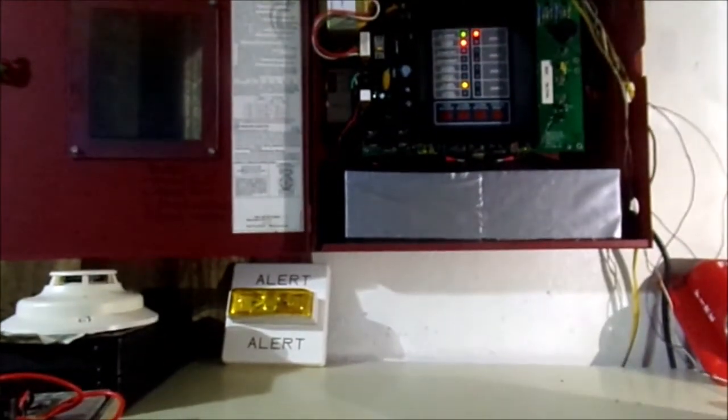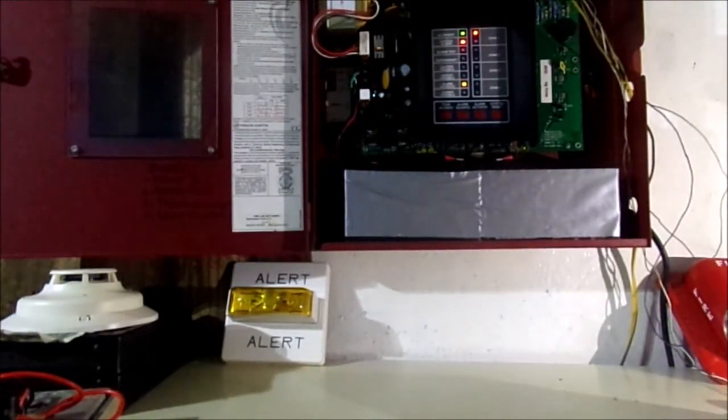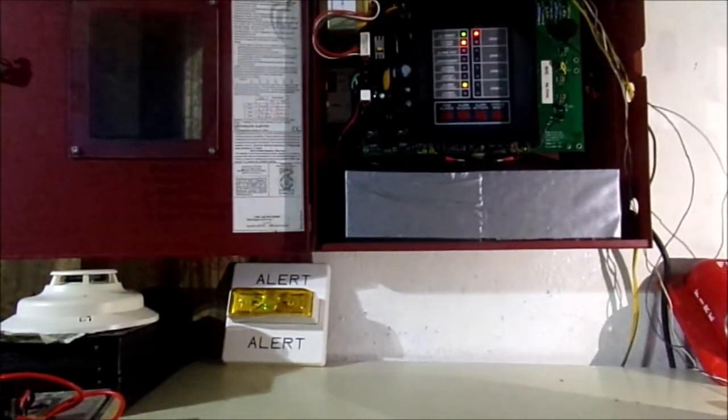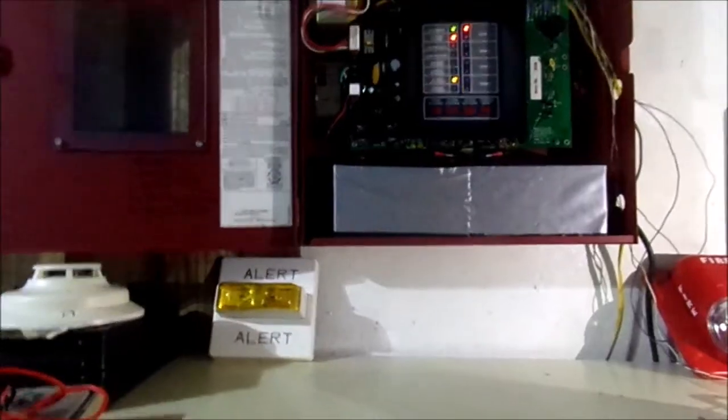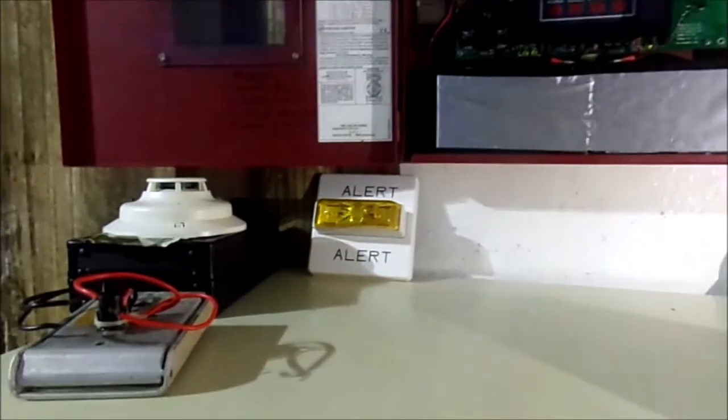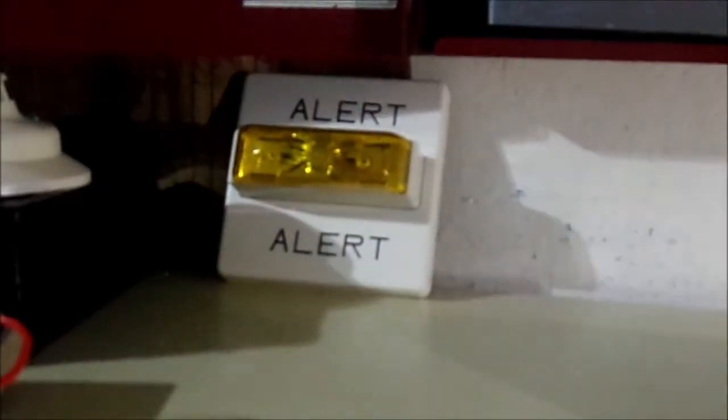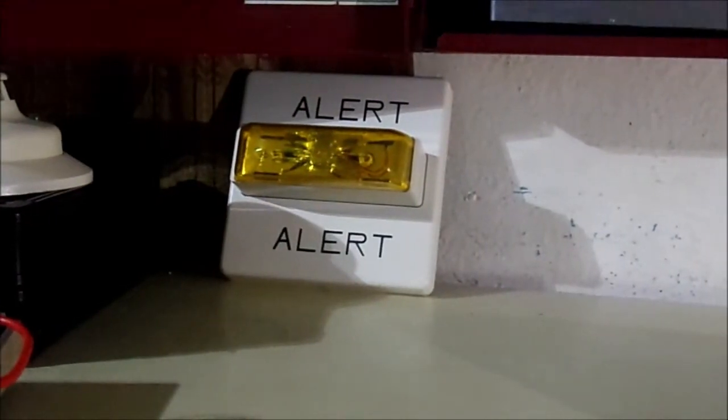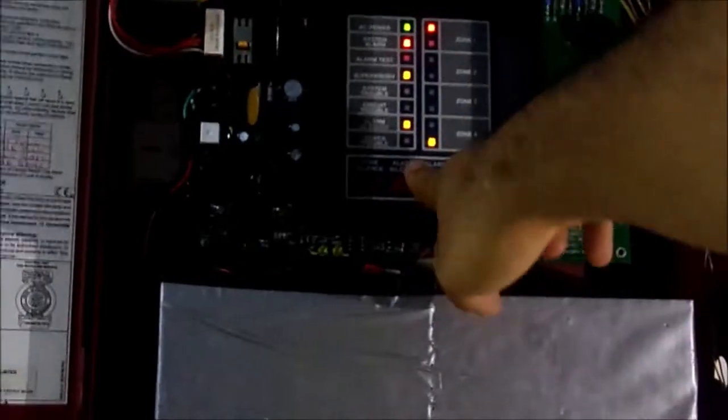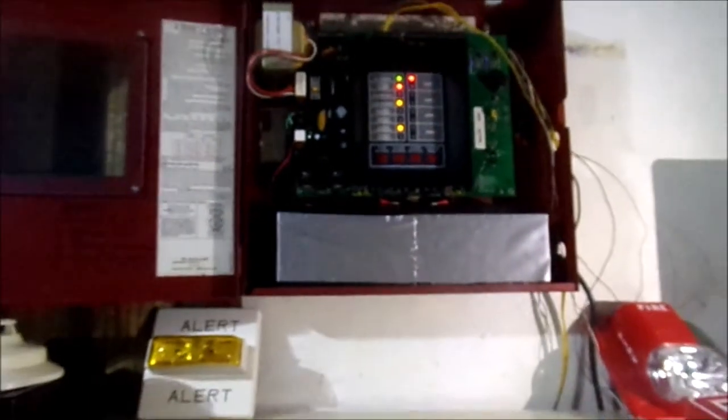The way this works is that you cut the jumper, which is behind here. I can't show you right now, but there's dip switches. What you do is set one of the switches down to Supervisory, and make sure you have one of the jumpers up there cut off. There's a jumper right behind here. You got to cut one of them off in order to have this Supervisory to work. But I'm going to demonstrate how this Supervisory worked by shorting the circuit. Don't do what I'm doing unless you know what you're doing, okay? There we go. The piezo tone silence is silence of piezo. And you can see that the Supervisory is flashing right now. And to stop it from flashing, you just put alarm silence. And there we go. That's basically how it works.